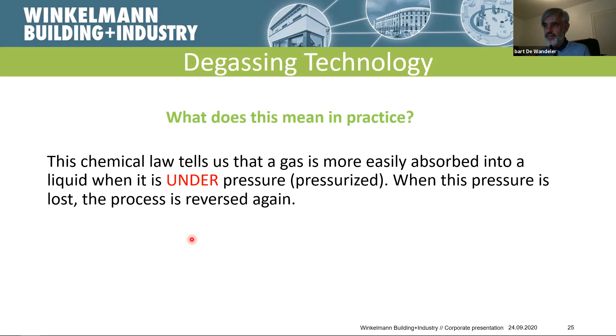A closed system is always under pressure, whether low, medium or high. All the nitrogen and oxygen is actually kept in the water, related to the pressure. When we relieve this pressure, like with the Servitec degassing system from Reflex, we can erase all those gases, including nitrogen, which is also very negative in a closed system loop.